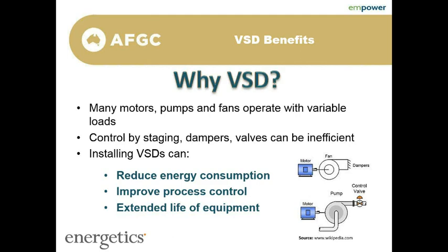Usually this is because there's smooth start operation to the motors, so rather than having a large current surge when you start up, you can have a much smoother gradual ramp up into operation. For the same reason, there's reduced wear on motors as they're not running 100% or even more. There's reduced wear and tear, and then there's also the electrical protection side of things. It insulates your equipment a bit from under and over voltages and other issues.